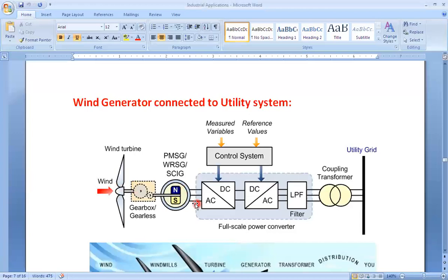Then how do we obtain this 50 hertz frequency with a proper three-phase AC supply? Simply, we apply the output of the alternator, that is the three-phase AC supply generated, to this AC to DC rectifier, right? It rectifies the AC voltage, and by triggering this phase control rectifier unit, we can control the output DC voltage across the input of the inverter.